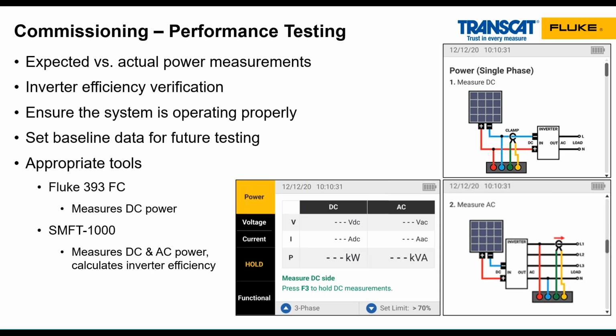And in order to test the DC power, we need to get all of those current carrying conductors, the negatives in this case, into that clamp. So if we have an inverter with a large number of circuits, it's going to be kind of challenging to physically get it into that clamp. The 393 clamp meter and the upcoming 283 clamp multimeter, which comes with a wireless current clamp, also 60 amp rated, are capable of measuring DC power. You'd have to separately measure AC voltage and current, measure and calculate that power, and then calculate inverter efficiency to use that tool.